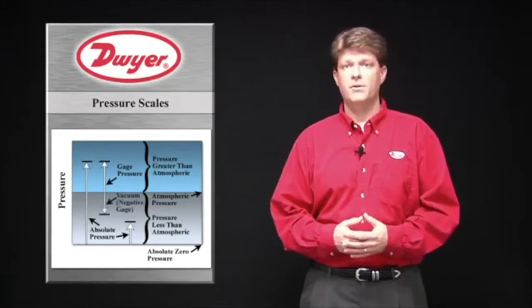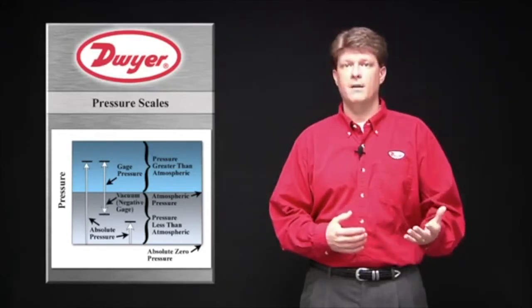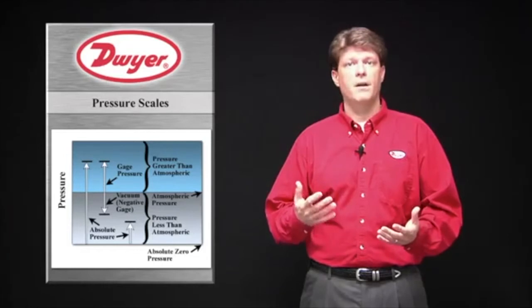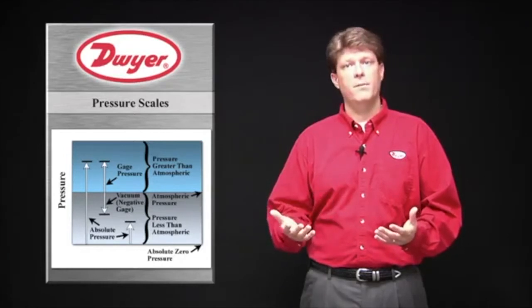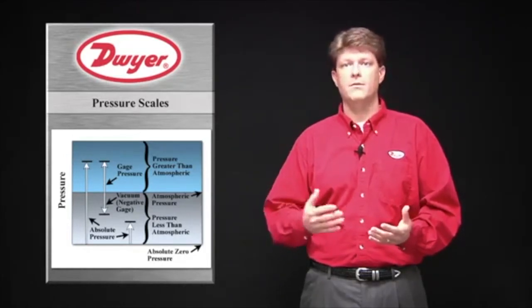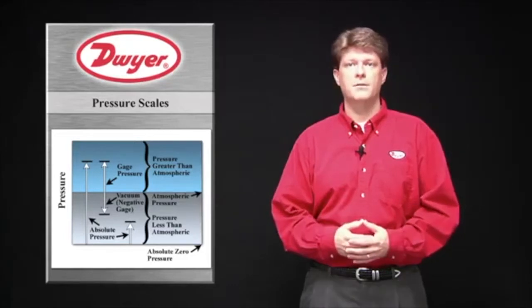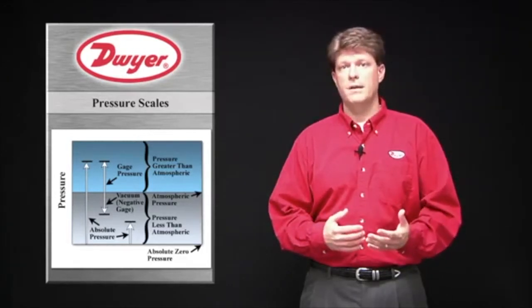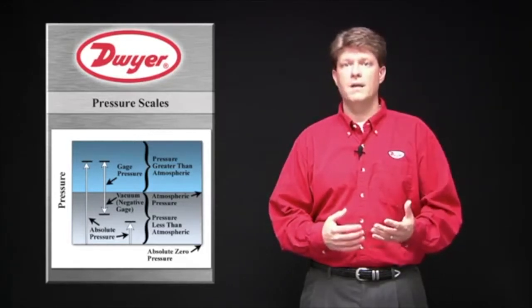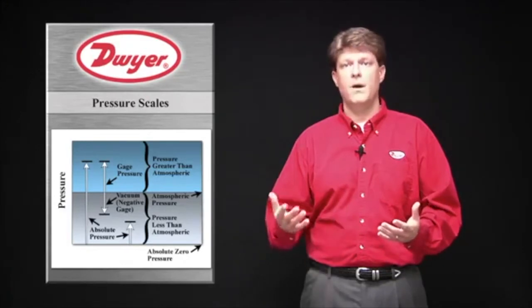Gauge pressure becomes negative when reading in a vacuum. Gauge pressure can vary as atmospheric pressure changes from altitude or weather patterns, which will affect high accuracy applications. Most pressure reading instruments read gauge pressure, as the reference side of the sensor is open to atmospheric pressure.